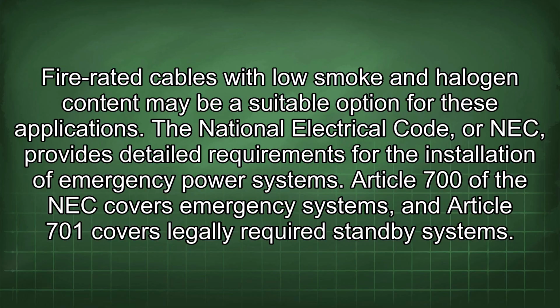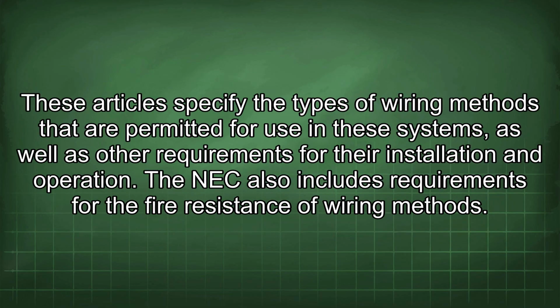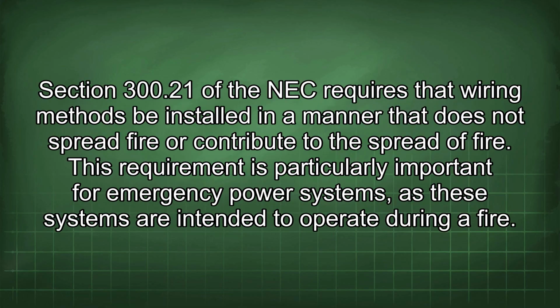The National Electrical Code, or NEC, provides detailed requirements for the installation of emergency power systems. Article 700 of the NEC covers emergency systems, and Article 701 covers legally required standby systems. These articles specify the types of wiring methods that are permitted for use in these systems, as well as other requirements for their installation and operation. The NEC also includes requirements for the fire resistance of wiring methods. Section 300.21 of the NEC requires that wiring methods be installed in a manner that does not spread fire or contribute to the spread of fire. This requirement is particularly important for emergency power systems, as these systems are intended to operate during a fire.